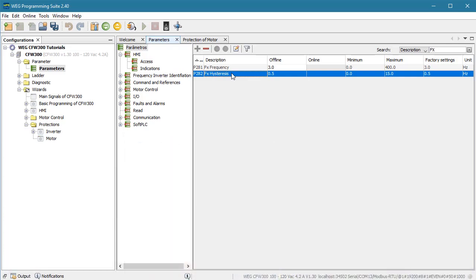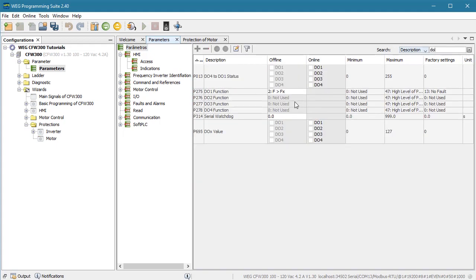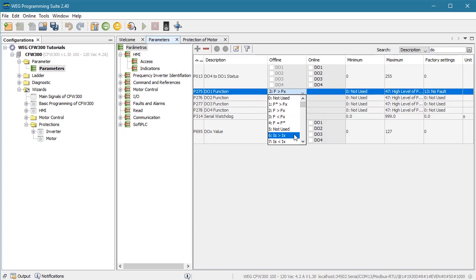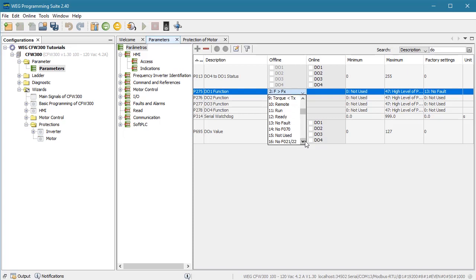There are lots of different things that digital relay outputs can be used for: Is the reference frequency above the threshold? Is the output frequency above or below a threshold? Is the reference frequency equal to the output frequency? And you can do similar things with current and torque. You can indicate if the drive is in remote mode, if it is running, if there are faults, etc. This drive gives you lots of options so use them to your advantage.